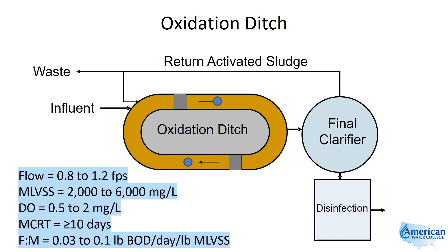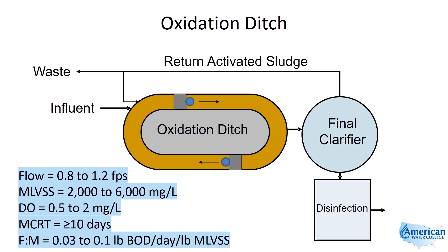The dissolved oxygen level is controlled by the depth of the water, which determines how deep the rotors and brushes go into the water to increase the exchange of oxygen through surface agitation. Dissolved oxygen levels are lowest just prior to the rotors, and the operator should maintain the dissolved oxygen at 0.5 to 2 milligrams per liter at this point.